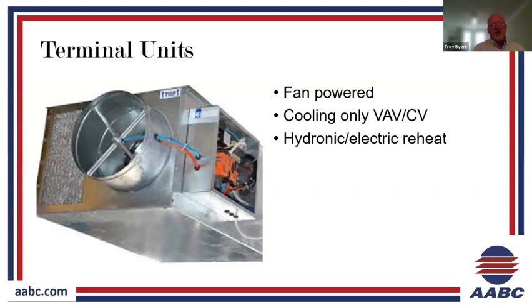So when we approach this terminal unit in an existing building, we want to pay attention to the filter on that unit and see if we've got a filter there to begin with, which might lead to some other maintenance requirements. But we want to pay attention to the filters on that unit. We want to look at those velocity pickup tubes that are shown there and verify the integrity of those tubes, because that's what's controlling the airflow based on a differential pressure sensor that they're connected to. So we want to make sure that that unit is calibrated. So measuring the airflow at the distribution or measuring the total airflow at the inlet of that box with our TAB instruments and comparing that measured airflow with the reported airflow in the building automation system.